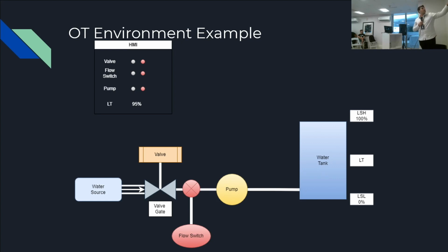And if the level where we want the water to be is higher than the one we marked in the original logic, let's say we establish the tank to be filled at 80%, and in this case it's 95%, shut down everything and don't allow for water flow.